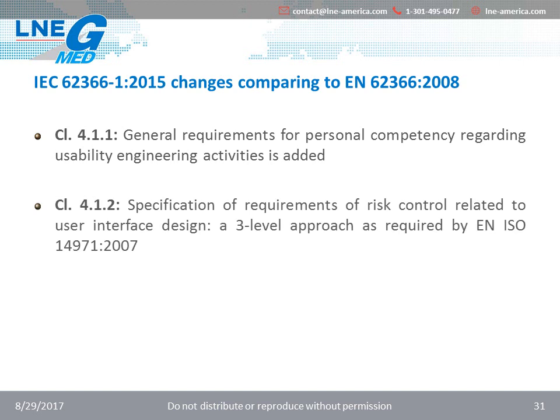Clause 4.1.2, a three-level approach as required by Risk Management Standard EN ISO 14971 2007, has been added to control risks related to user interface design. These three levels are inherent safety by design, protective measures in the medical device itself or in the manufacturing process, and information for safety.